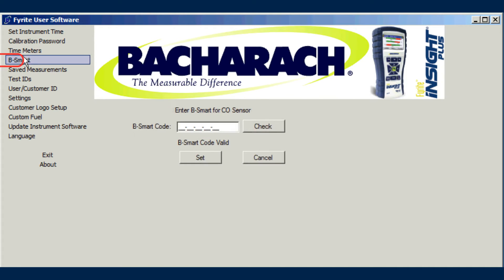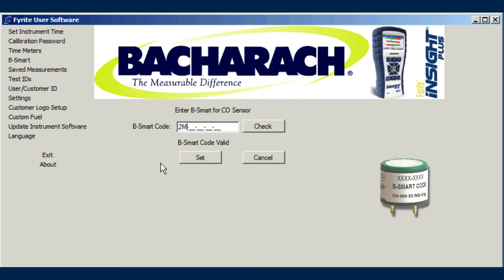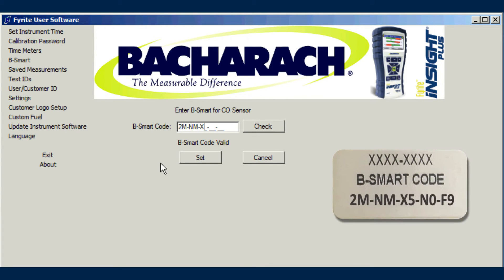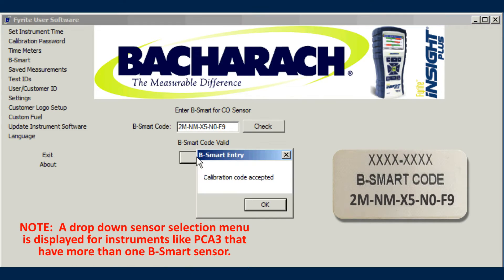Use the B-Smart menu item to enter new B-Smart codes to calibrate the instrument to match the B-Smart sensor's internal calibration data. Entering your B-Smart code through the software interface may be more convenient than using the instrument's keypad. Simply select the sensor to calibrate from the drop-down menu, then enter the corresponding B-Smart code from your new B-Smart sensor and click the Set button.